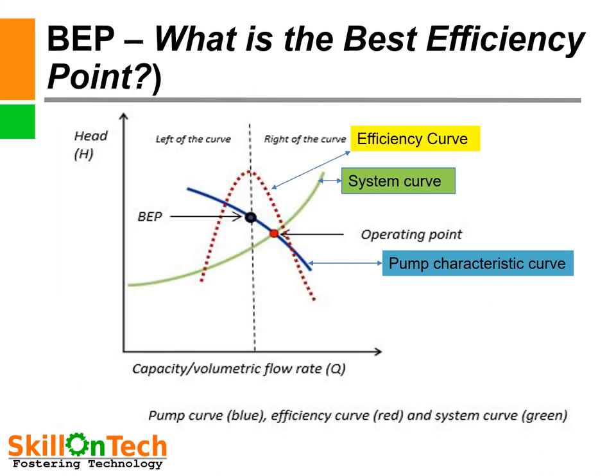What is the best efficiency point (BEP)? You can see an HQ curve and an efficiency curve in this slide. The line intersecting at the highest point of the efficiency curve gives the best efficiency point. However, in industry, pumps do not operate at this point because they must operate against a system head curve. Where the system head curve intersects the HQ curve is the actual operating point of the pump.